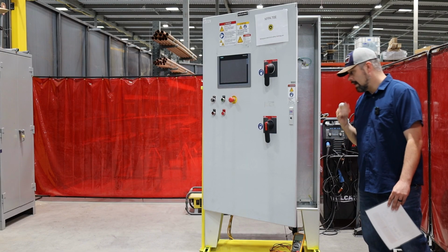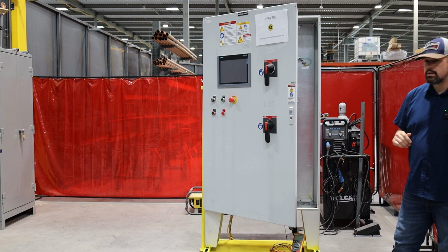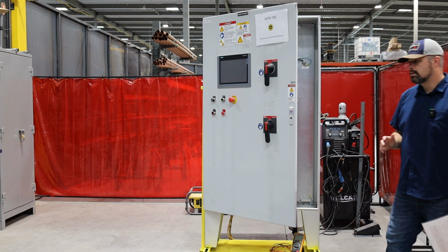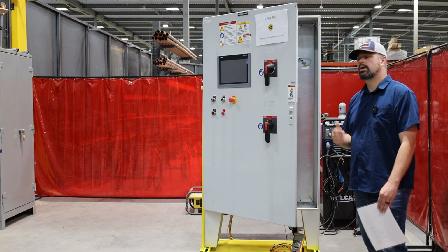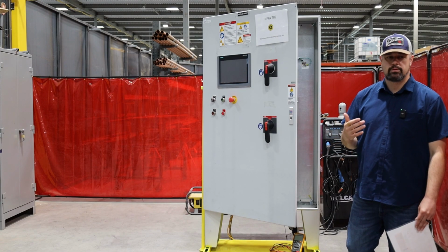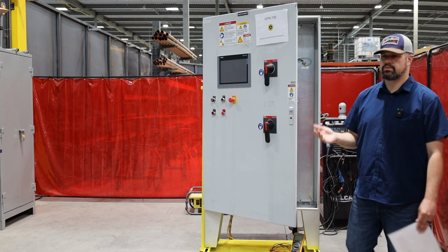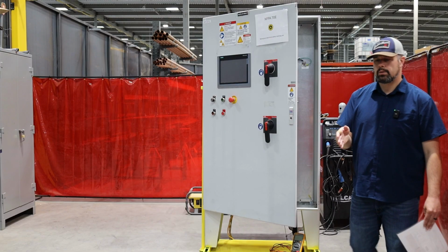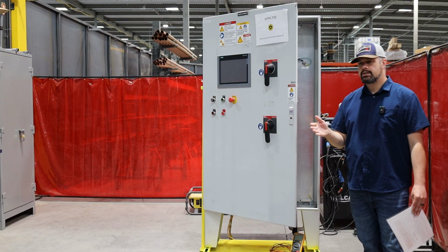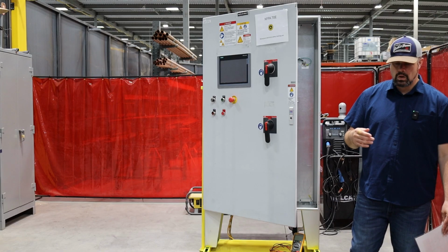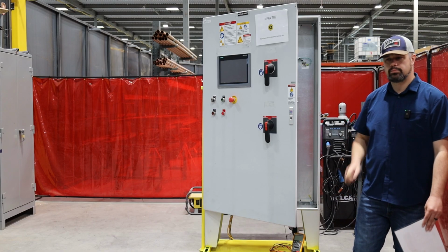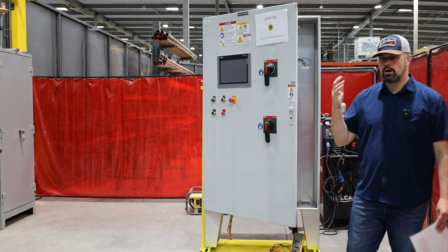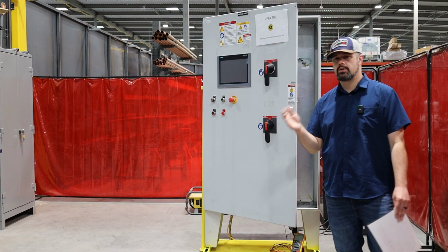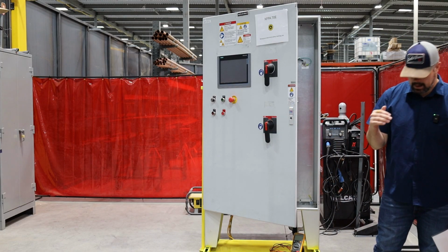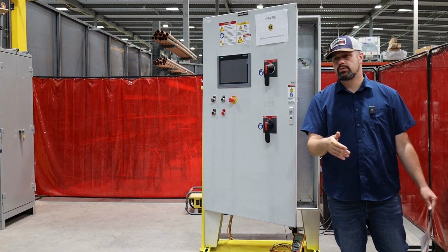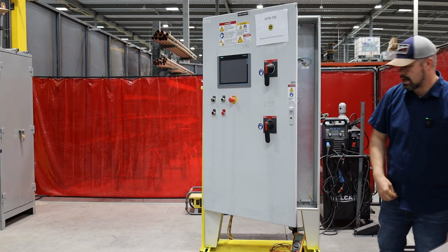Okay. Now let's say that we open it and the breaker is not tripped. So now maybe we're at the point where we're going to take some verification of voltage, the presence of voltage readings. Again, as level 1, having successfully passed the NFPA 70E training plan, you are authorized to grab a meter, put it on volts, and do a verification of 400 up to 480 volts to verify the presence of voltage, or the absence of it if you're doing live to live.